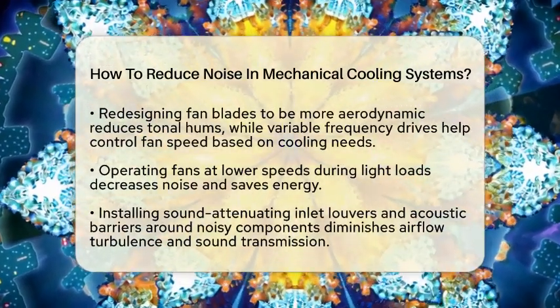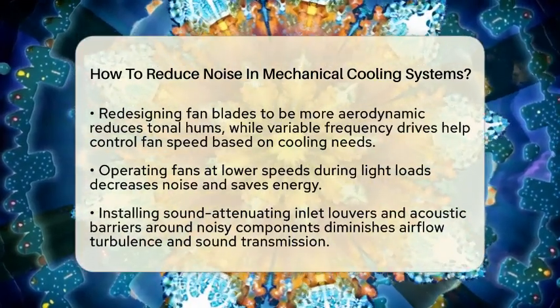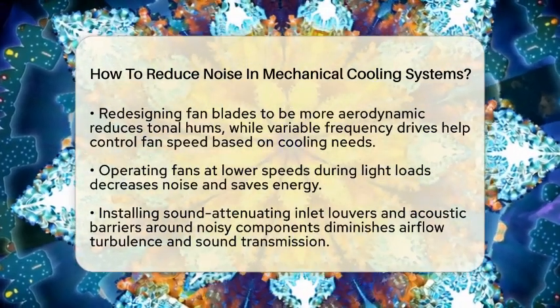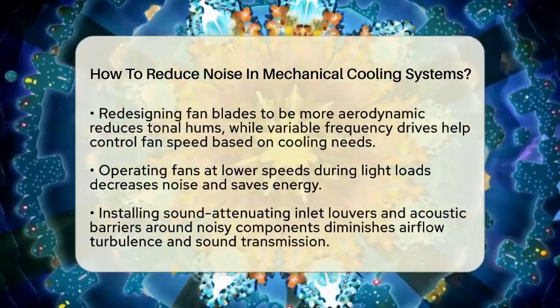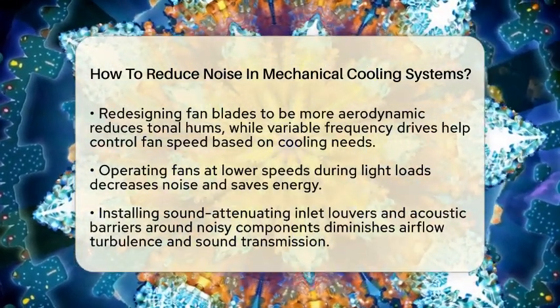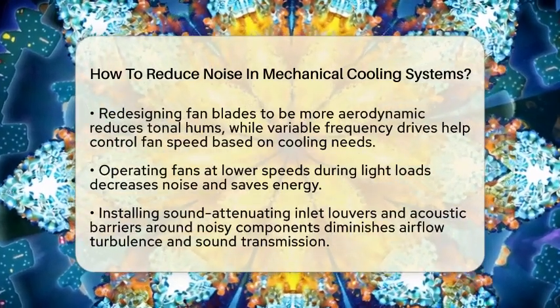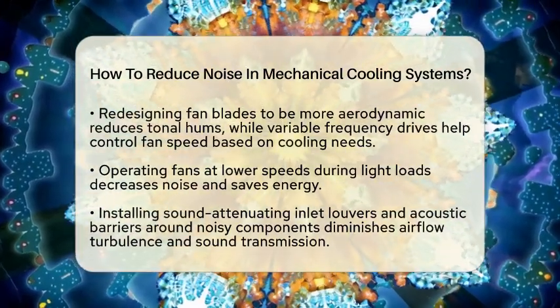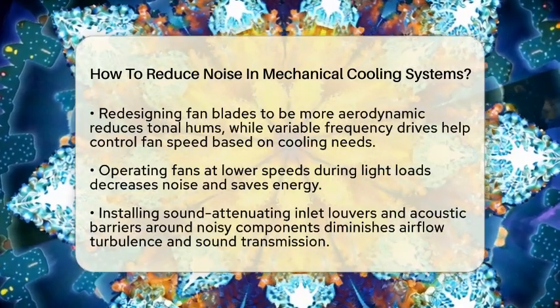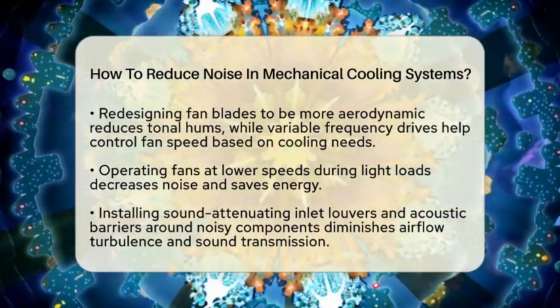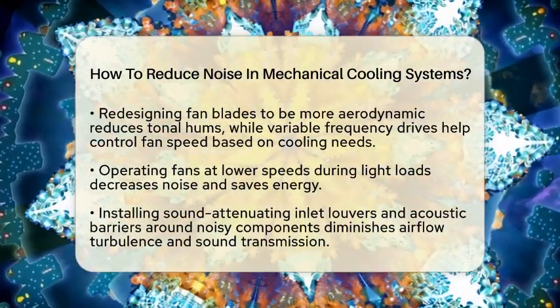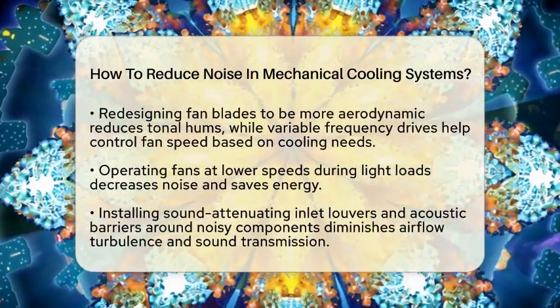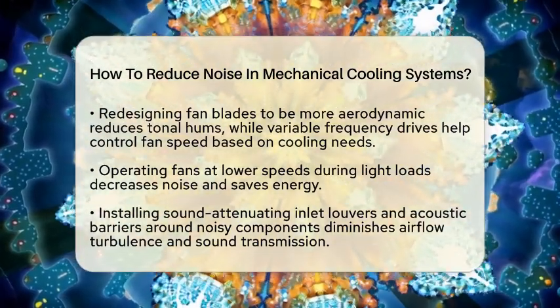Fan noise is another big contributor. To reduce it, you can redesign fan blades to be more aerodynamic. This helps minimize the tonal hums caused by blade passage frequencies. Using variable frequency drives allows you to control fan speed based on cooling demand. Running fans at lower speeds during light loads reduces noise and saves energy.